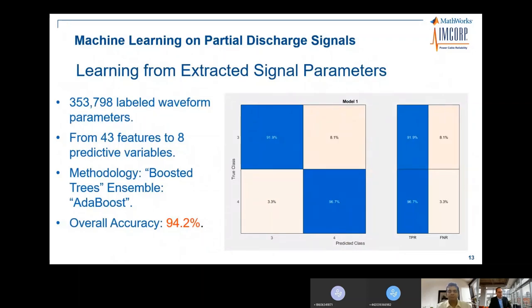The machine learning approach used a boosted tree methodology on a data pool of 353,000 labeled waveform parameters. The waveforms were labeled by human expert analysts using specific signal processing tools to classify partial discharge signals. Out of 43 extracted features, only 8 are necessary to achieve an overall accuracy of 94%. The goal is to find out how much closer to 100% is achievable.